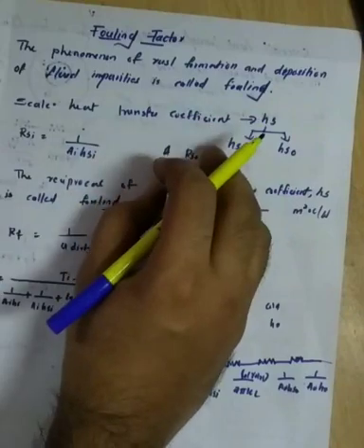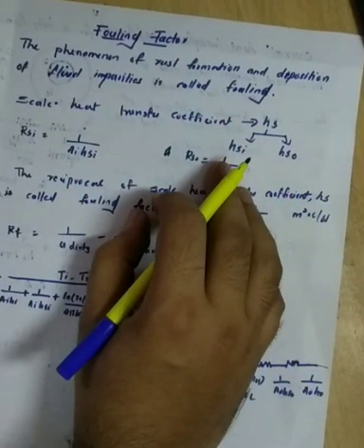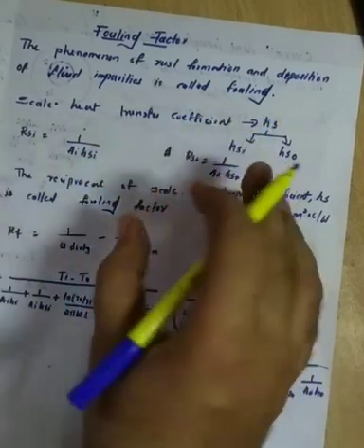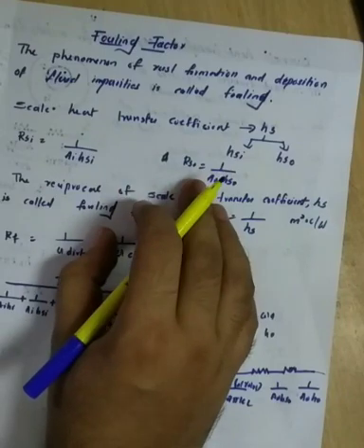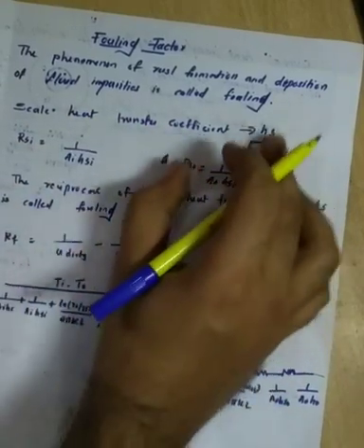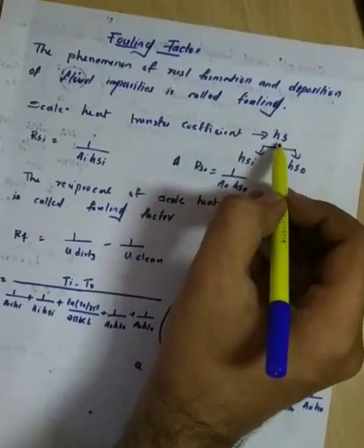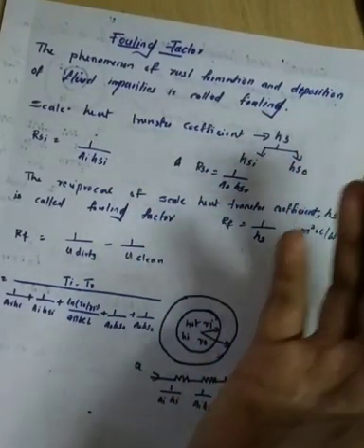Due to this, the thermal resistance of the heat exchanger increases, and eventually the performance of the heat exchanger lowers. The effect of scale on heat flow is considered by specifying its heat transfer coefficient. So the value of hs is used to specify the effect of fouling on the heat exchanger.